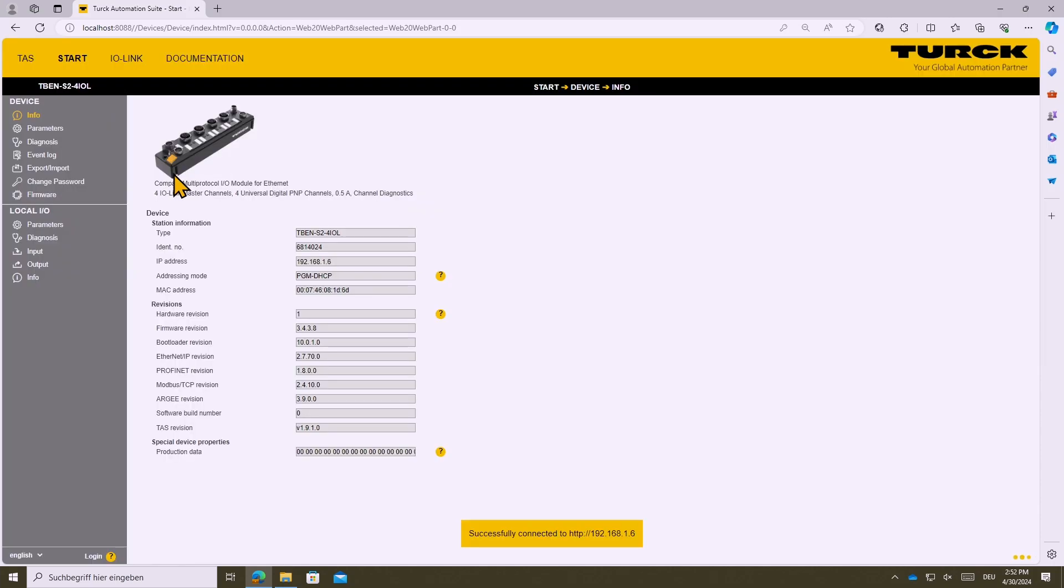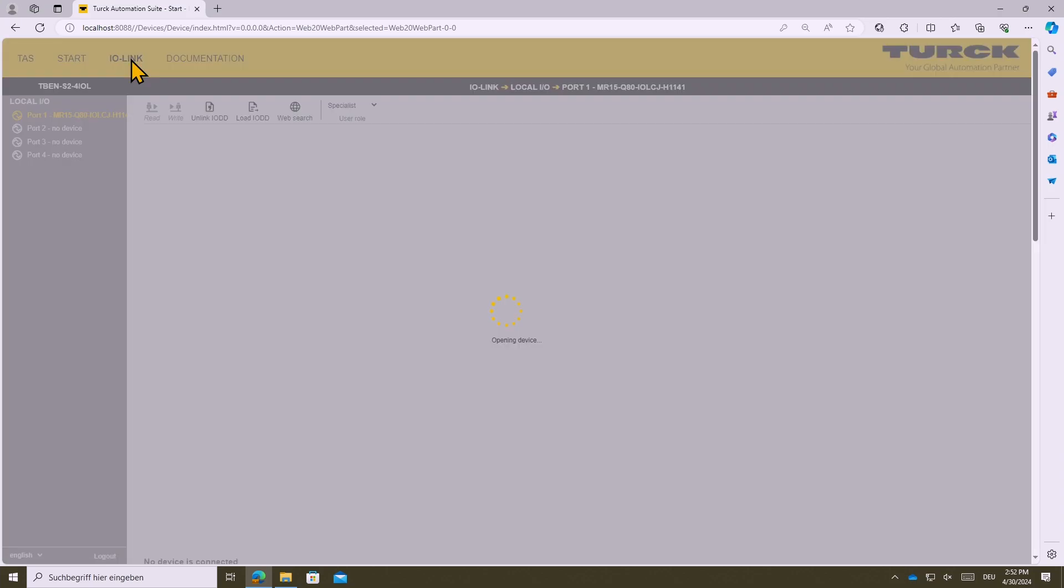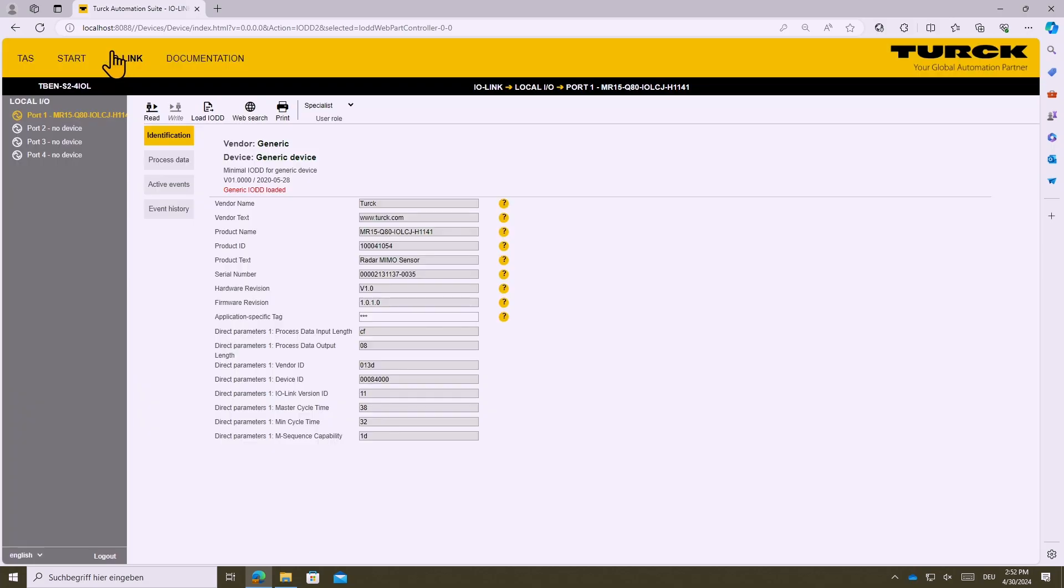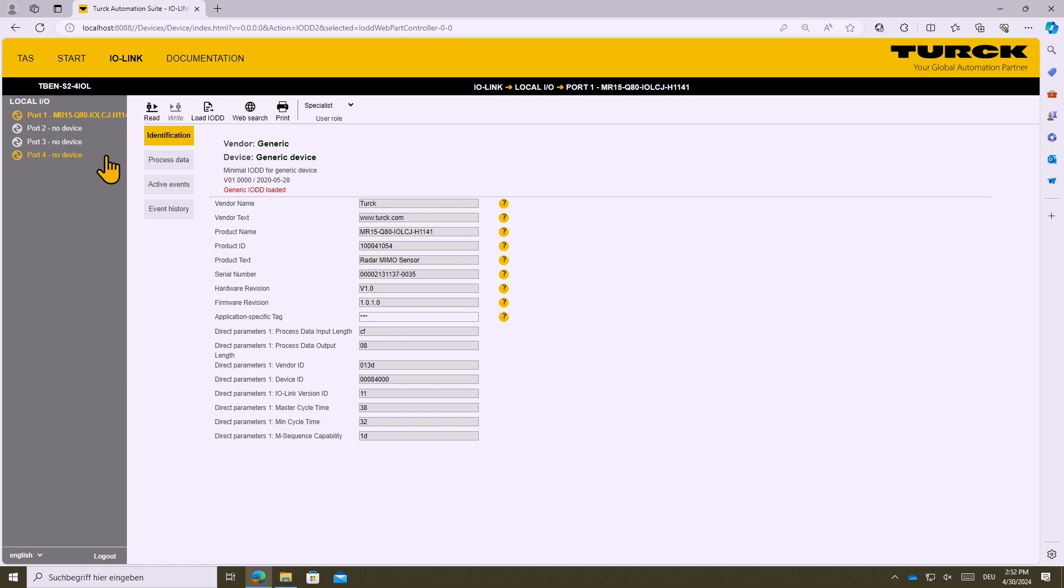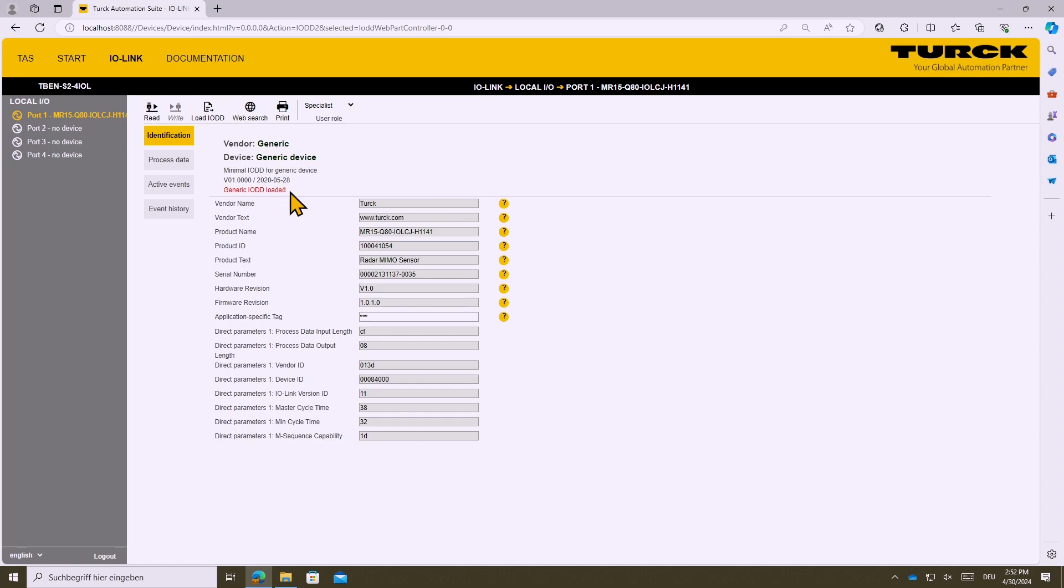your IO-Link master and by clicking on this icon open in TAS. TAS will open. By entering the login data, the default ones, you can access the IO-Link communication tab by clicking on IO-Link.